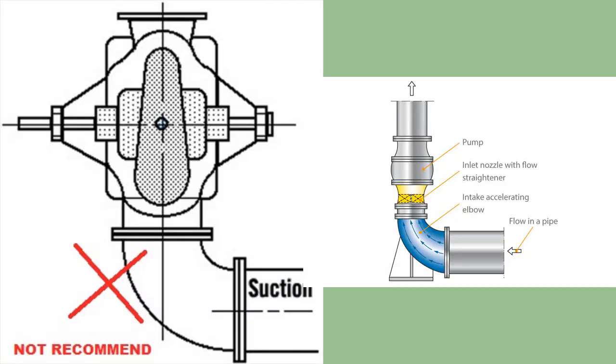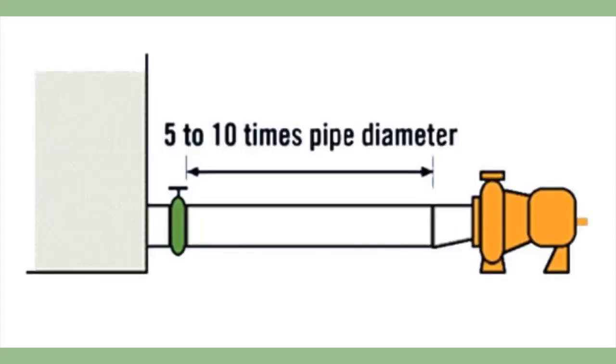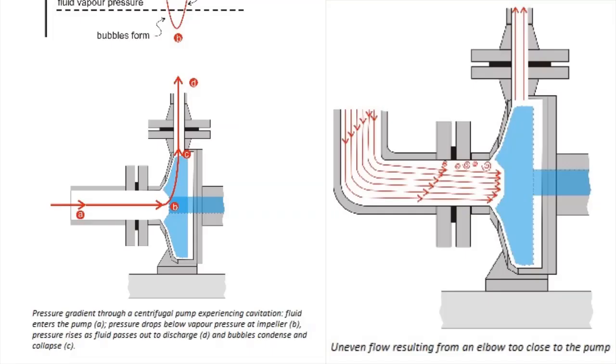Number four, eliminate elbows mounted on or close to the inlet nozzle of the pump. Include five to ten pipe diameters of straight run pipe between the pump inlet and elbow. This helps eliminate the side loading of the pump impeller and creates uniform flow.